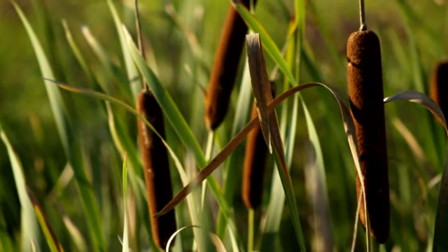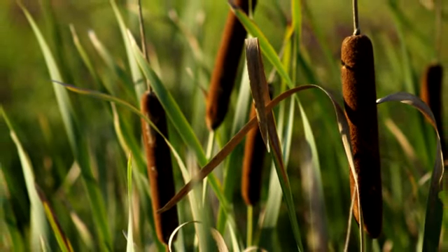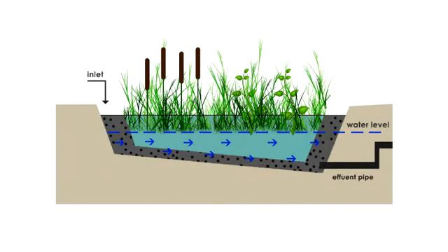the wind, and direct sunlight. Horizontal subsurface flow systems are large gravel and sand-filled channels planted with aquatic vegetation. The bed is 0.5 to 1 meter deep and is lined with an impermeable liner in order to prevent leaching. Wastewater is intended to stay beneath the surface of the porous media, flowing within the pores and around the roots and the rhizomes of the plants. The bed should be wide and shallow so that the flow path of the water is maximized. The bottom slope is normally 1%.